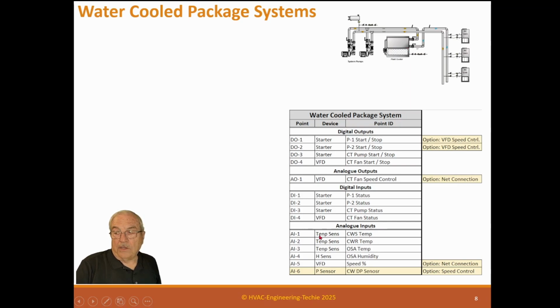And then we have analog inputs. We have a temperature sensor for the condenser water supply temperature and the condenser water return temperature. We have an outside air temperature and an outside air humidity sensor. Now, these two may be coming in from global points, but we need to have those. If they're coming in as global points, they don't burn points on a controller. They just come into the software. But if we don't, we have to have them out there. And many times in the central plant is where the outside air temperature and outside humidity sensors are that broadcast to the rest of the system. AI5 is the VFD speed percentage, what speed we are actually running.